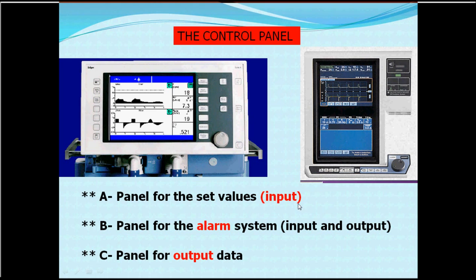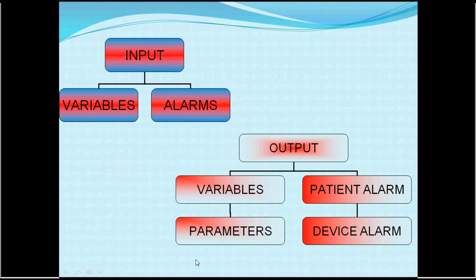The alarm is patient-specific, not a common alarm for all. For example, if the patient's tidal volume is 300 ml, you set an alarm at 250 ml. If the peak pressure is 10, you set an alarm at 15. If it drops to 8, you set an alarm. These values vary according to each patient. The third part is the output data.